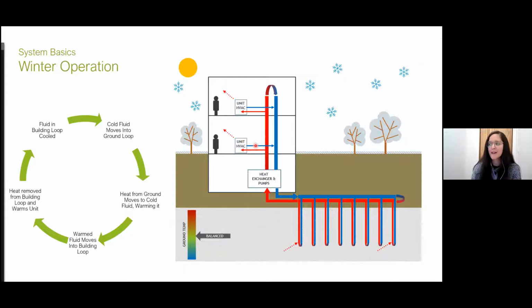The return fluid that goes back into the building loop is cooler. It then goes back down into the ground, where it circles through the main geothermal loop, and the ground temperature heats the fluid back up again, and the cycle continues and continues. What happens with that, though, if you're looking at just the winter season, is that compared to the starting point at the end of the winter cycle, your ground temperature will have cooled down a little bit because of all the heat that's been taken out to go and provide heat to the building.